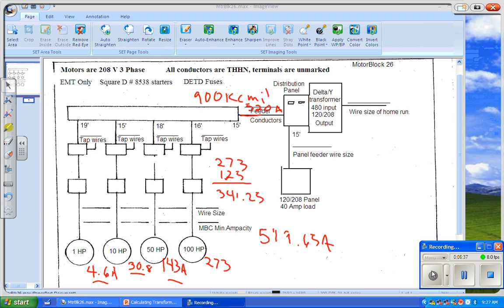Okay, so we're going to say that our total load on our transformer is going to be about 560 amps. Everybody agree with that? Now we've said that this thing is a delta Y, right? And we know that this thing is a step-down transformer from 480, right? 480, 480 because it's a delta, and it's stepping it down to 120, 208. So 208 is our line voltage, and 480 is our input line voltage.